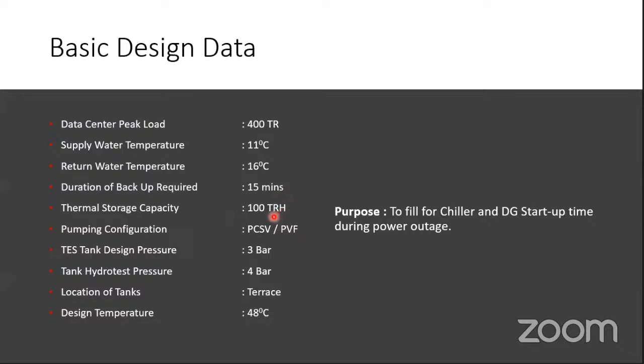It is also important to know the pumping configuration in this scenario, whether it is primary constant, secondary variable, or primary variable flow, because the schematics are different for both. We also need to know the design pressure of the thermal storage tank, the system pressure, and the working pressure. Hydro test pressure is done after the tank is manufactured, generally as per ASME standards, which is nearly 1.3 times the design pressure. So from constructional and integrity purposes, this data is also important.